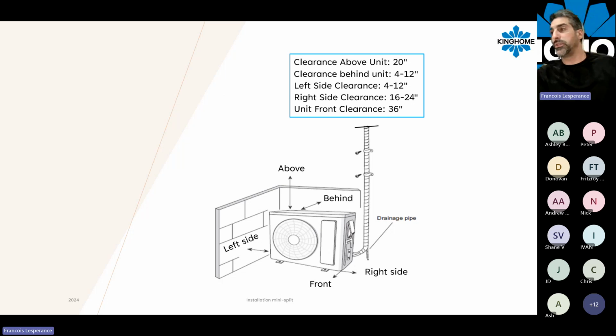So when we're going to install, or if you guys are going to do a call on an outdoor unit, it's pretty important to keep in mind the clearance all around the unit. Make sure the unit is getting enough air and can perform freely, so there's no blockage or restriction around the unit. One really important thing is what is going on in front of the unit.